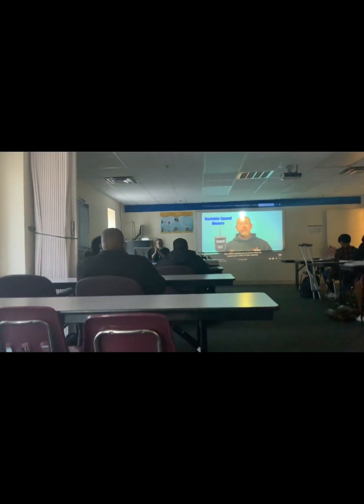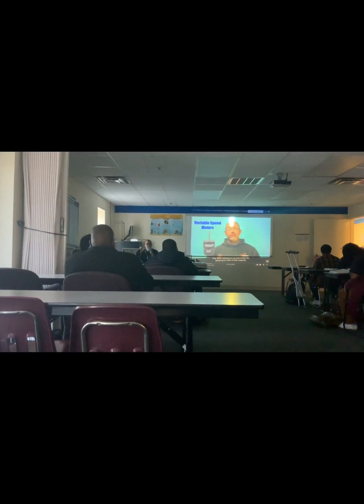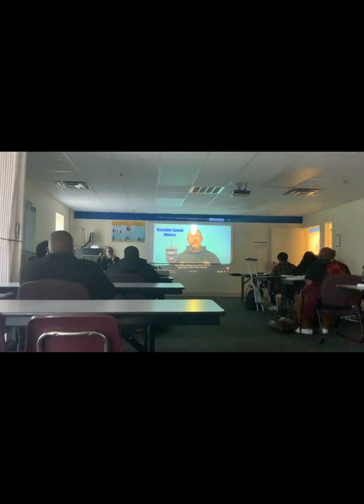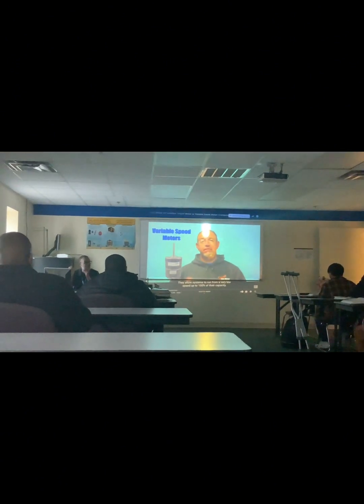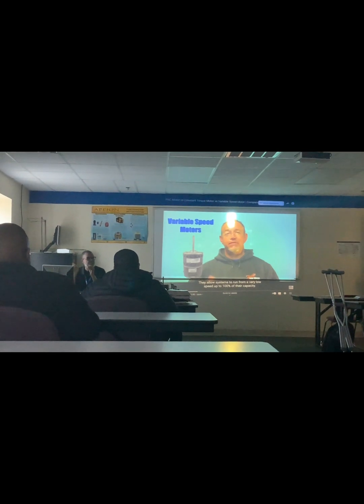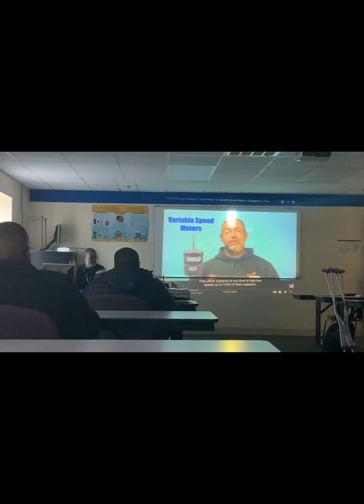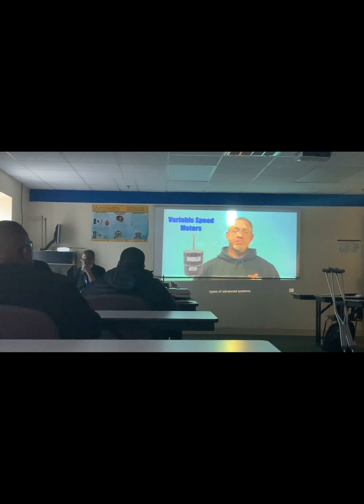They all have a specific job to do, or a specific ability to change the operation of a piece of equipment. That's all they do. They can make it space age if they want to. It still has to work primarily under those 3 conditions: pressure, temperature, and timing. Very low speed, up to 100% of their capacity. Being able to dial in the desired speed precisely makes them the motors that are best choice for all types of advanced systems.